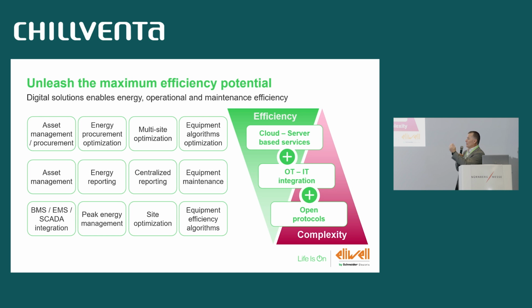If we go up one level, like integration with different systems - having the BMS managing humidity in the environment, in the supermarket - we can reduce defrosts, reduce the need for defrost. So we can balance the power used in the refrigeration system, the defrost system, the interval and duration of defrost, versus the power used in the HVAC system.